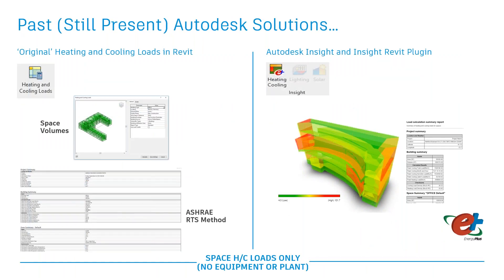Autodesk has a long history in this area, going back to the original heat and cooling load tool in Revit — about 14 years old — which was actually the start of the whole effort around GBXML with Revit. That still exists today but is limited in geometry and uses a radiant time series method. More recently, with Autodesk Insight and the Insight Revit plugin, we used EnergyPlus for heating and cooling load calculations. The key limitation with both was that there was no equipment or plant in the equation. This new systems analysis feature essentially overrides the need for these.